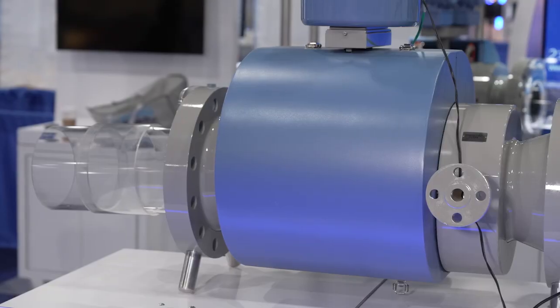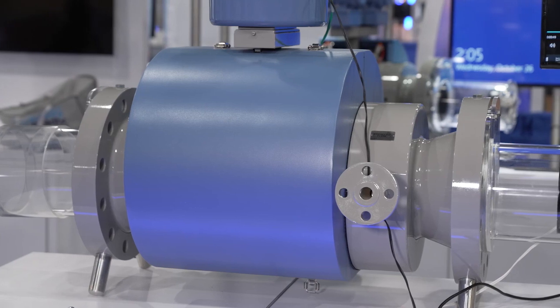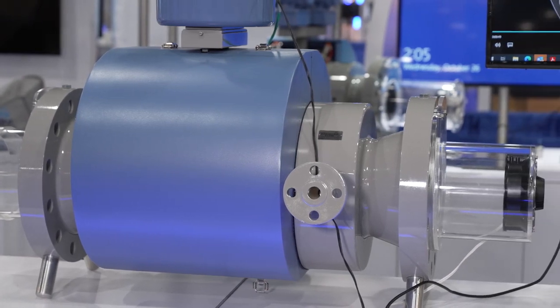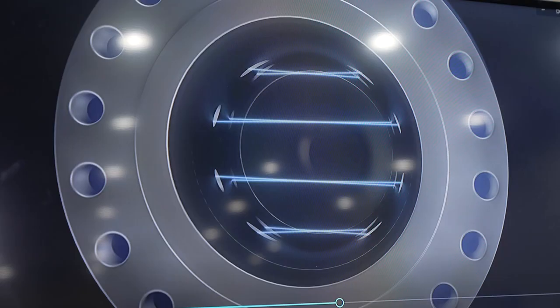We recently introduced the Rosemount 3418 eight-path gas ultrasonic meter, which is designed with a second set of four chords positioned in the mirror image of the first, as demonstrated here, allowing the meter to cancel out the effects of swirl and asymmetry in the flow.